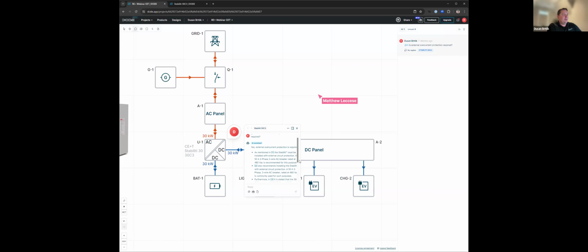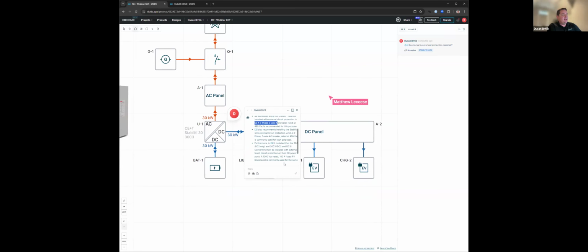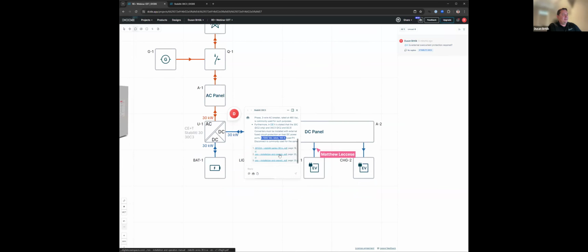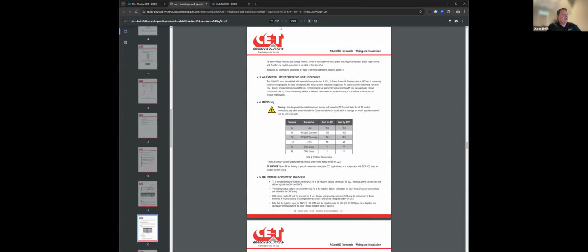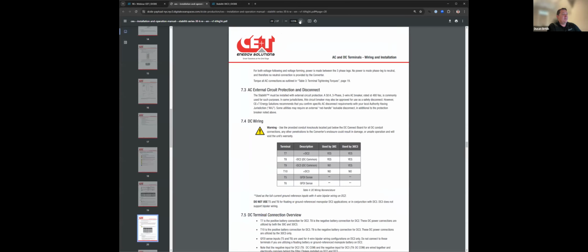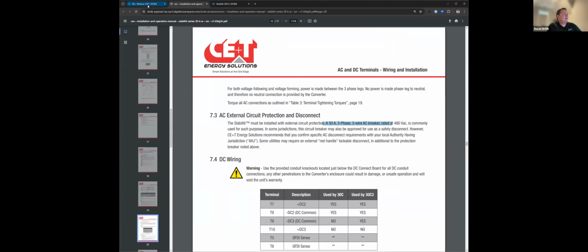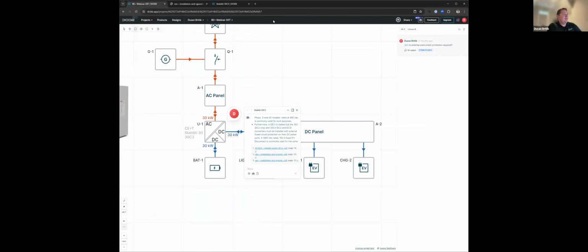The AI tool will return, at least for your Stabiliti series, that on the AC side we need to add a 50 amp, 3-phase, 3-wire AC breaker, and on the DC side we need a 1000-volt DC rated, 100 amp fuse. It also provides the references on where this information came from. In this example, it came from your application guides.